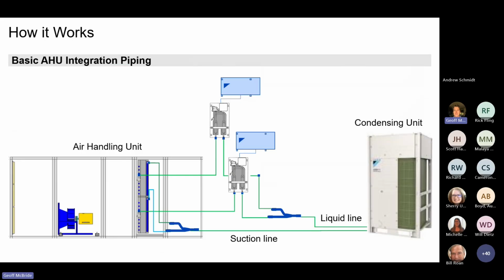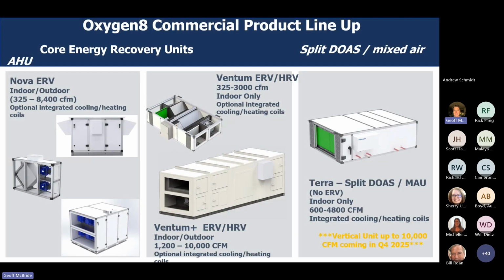This is the concept. When you're pairing it with an air-cooled heat pump, you're going to have a liquid line and a suction line that go to these expansion valves and control boxes. And then it will go to a third-party coil that can be in a third-party air handler. Again, we've got a big, long presentation that we can do on this subject. I'm just giving you a snapshot of it. Oxygen 8 and Daikin Applied are both going to be ETRS listed, which is this enhanced tightness requirement that's going to be very crucial to comply with ASHRAE 15 with A2L refrigerants.